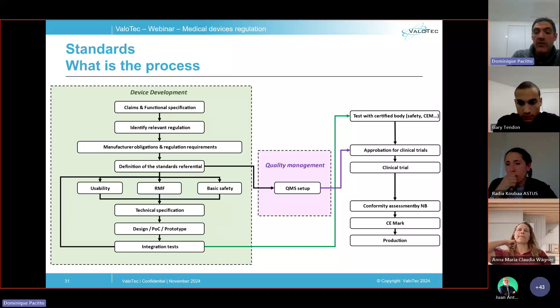When your prototype is ready and the traceability is up to date, your device can then be tested by certified bodies. Then you should follow the certification process shown earlier: approbation for the clinical test, the clinical trial, assessment by notified body, and so on. And at last, the CE mark can be issued, and the device is ready for production.